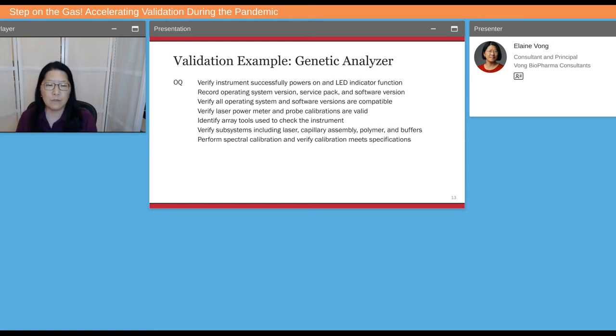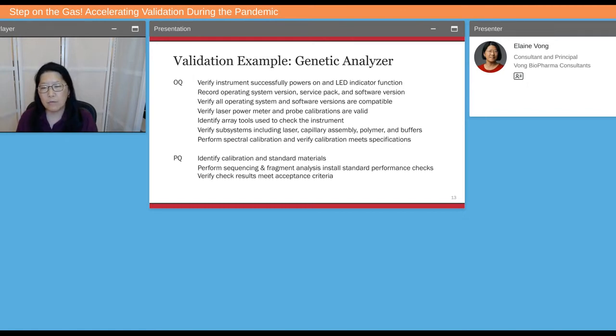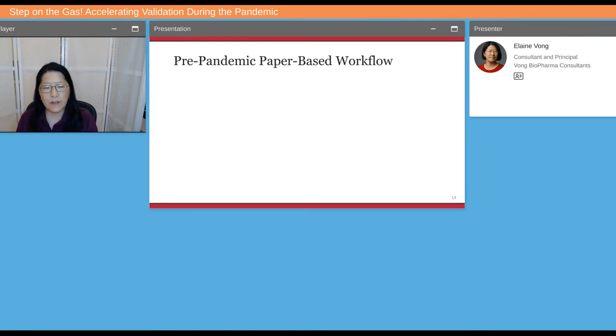Verify subsystems including laser, capillary assembly, polymer, and buffers. And performing spectral calibration and verifying that calibration meets the specifications. The PQ might consist of identifying calibration and standard materials, performing sequencing and fragment analysis, installing performance checks, and verifying that the check results meet the acceptance criteria.